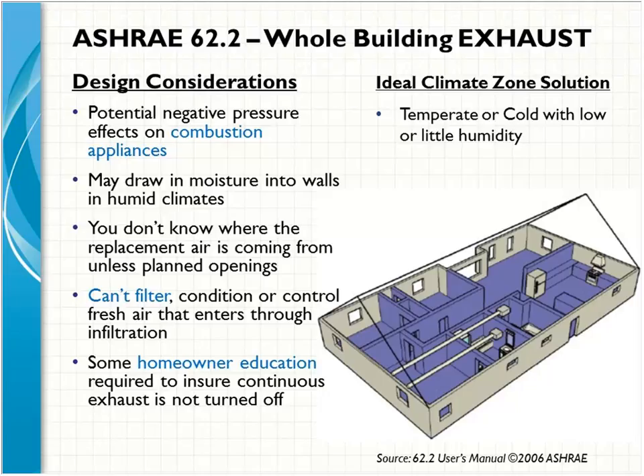But you'll see in the top right-hand corner that for northern climates, this is often the best approach, because if you're relying on dragging in cold air during the winter months to meet the requirement, that air can have a drying effect on the building shell. And when we talk about supply-only ventilation, we'll explain why that might not be the best for a northern climate. Another plus for exhaust-only ventilation is that it requires very little homeowner education. You set it up, do your calculation, program it to run automatically, and there are no filters to change, no interaction from the homeowner, and very little education that has to be done. And as I mentioned before, it's also usually the least expensive system to use. So let me just take a look at this.